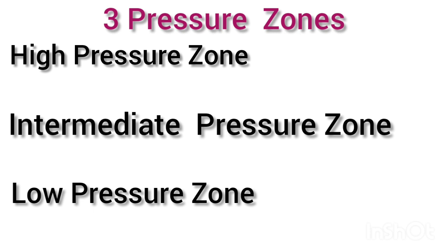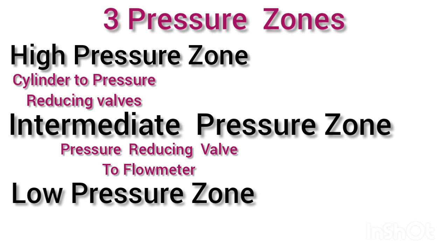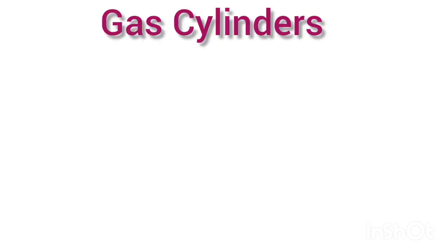The high pressure zone starts from the gas cylinders to the pressure reducing valves. The intermediate pressure zone starts from the pressure reducing valve till the flow meter. From the flow meter to the common gas outlet is the low pressure zone. Now, the gas cylinders.